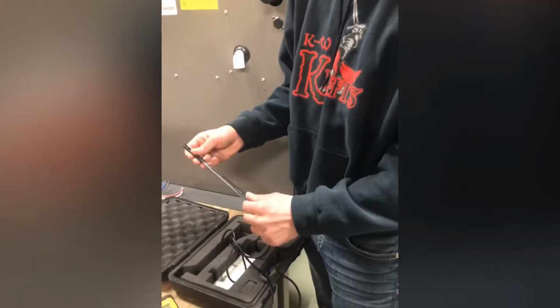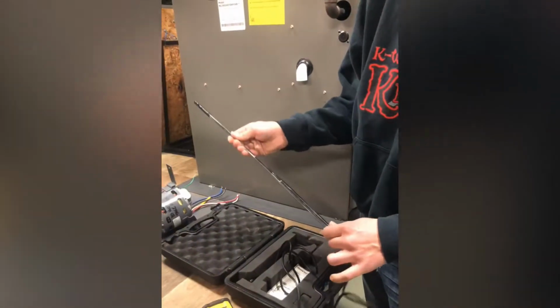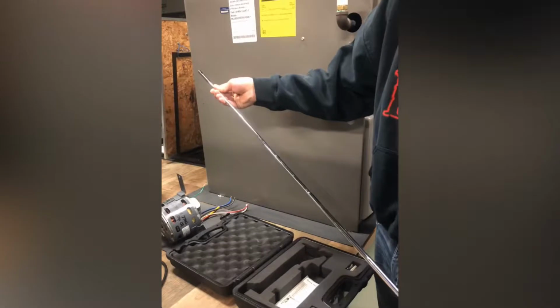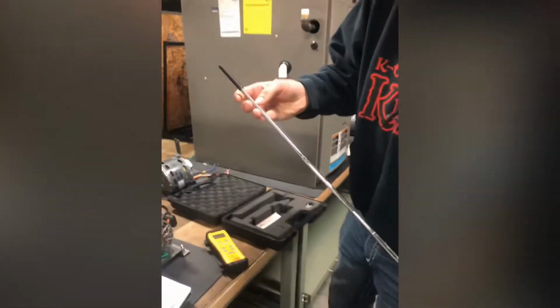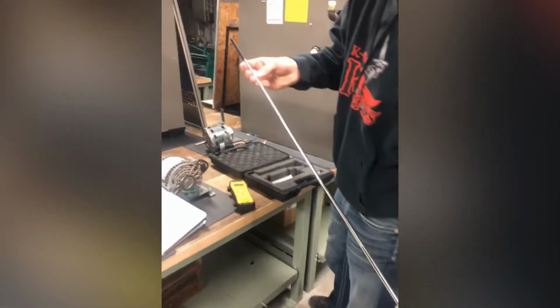So you're going to want to take your wand, and the wand actually extends to make it easier to put it in ducts that are a lot larger. And if you look closely on the side of the wand, there's measurements, so you know how far you can put it inside a duct. And on the very tip of the wand, it's got this bigger bubble, which is the thermometer reading to measure the temperature, and that is a hot wire that will measure the CFM and the airflow across the duct.